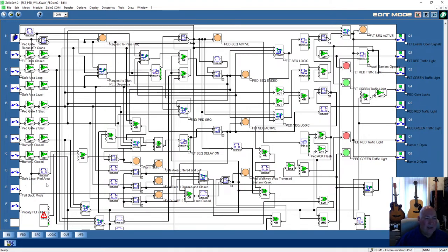We're going to introduce that. And then also we've got to introduce a change of priority from forklift truck to pedestrian. At the minute, by not connecting a switch, we are in forklift truck priority, and you request a pedestrian crossing. But there are some scenarios on a different site where they want the pedestrian to have the priority, and the forklift truck will have to request instead. So it needs to be switchable. I've allowed for a switch just in case.